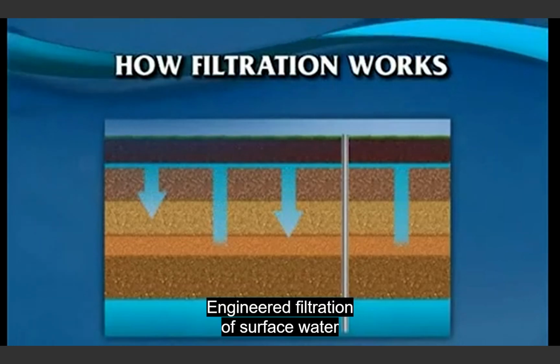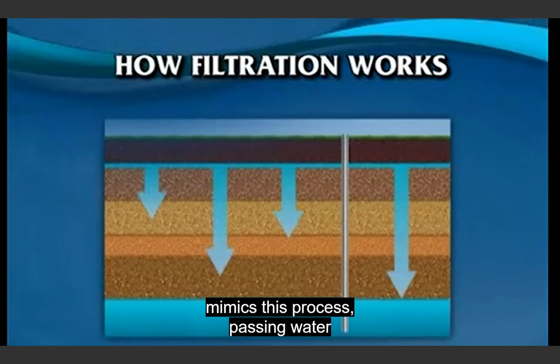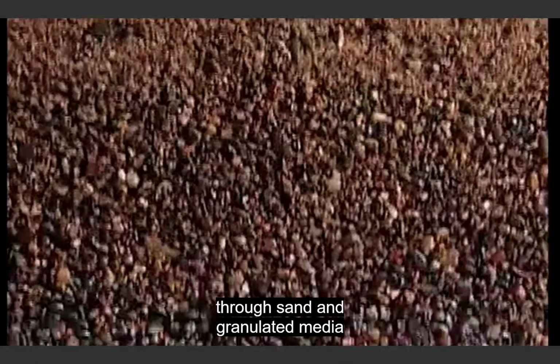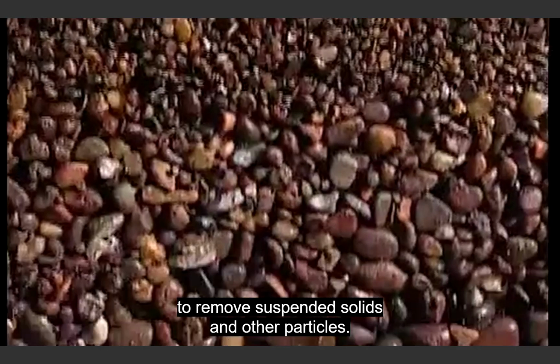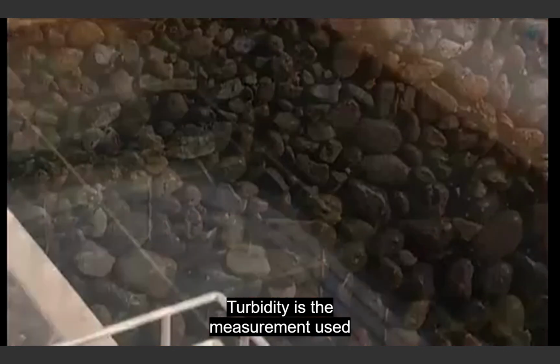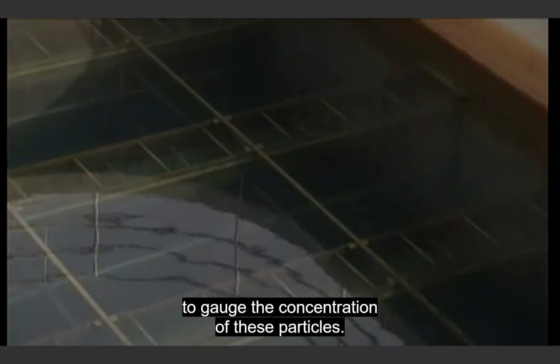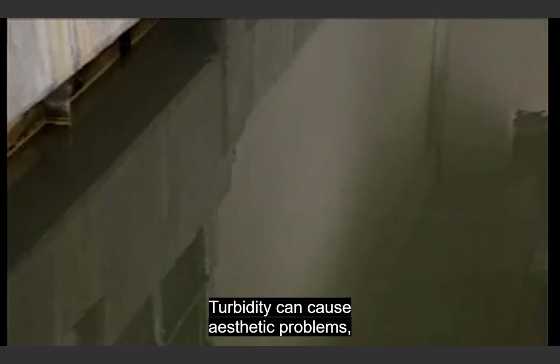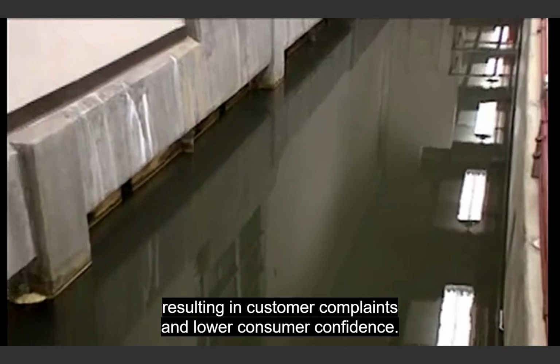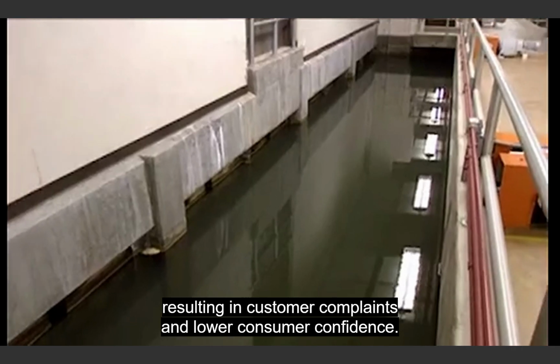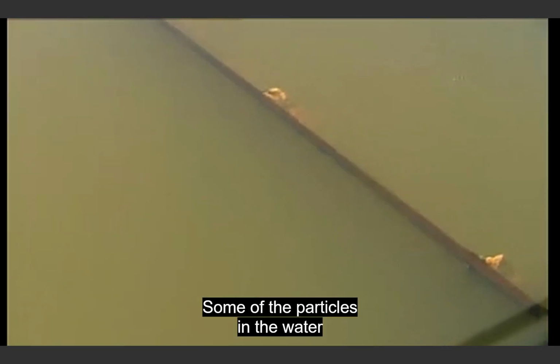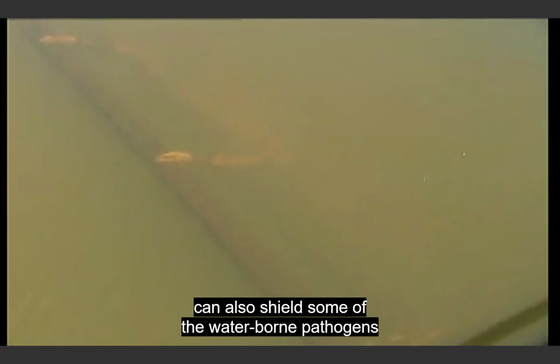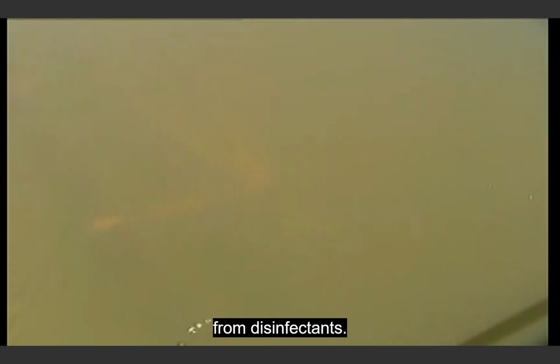Engineered filtration of surface water mimics this process, passing water through sand and granulated media to remove suspended solids and other particles. Turbidity is the measurement used to gauge the concentration of these particles. Turbidity can cause aesthetic problems, resulting in customer complaints and lower consumer confidence. Some of the particles in the water can also shield some of the waterborne pathogens from disinfectants.